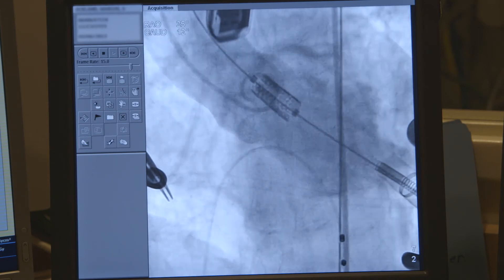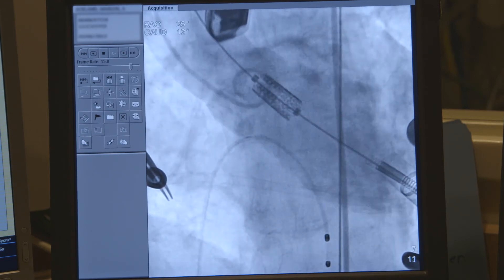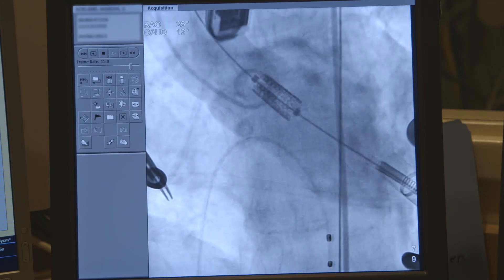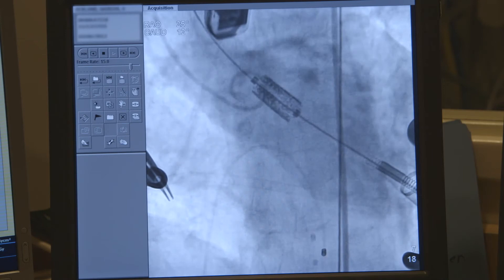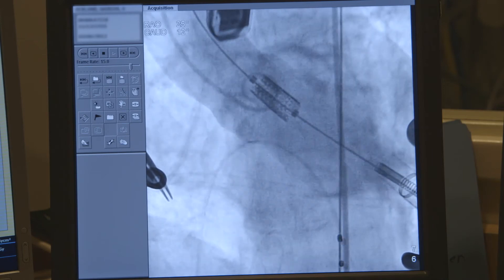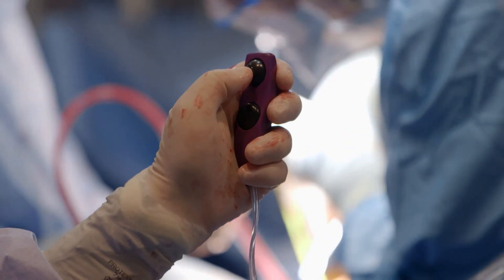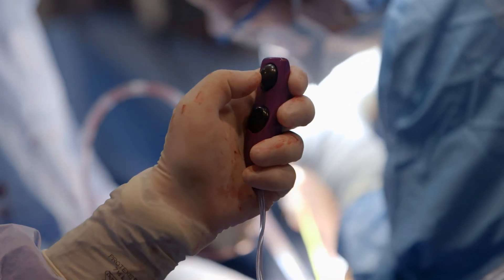Localization of the prosthetic valve to the native valve is very important and that's usually done with injections of contrast. Sometimes you need a little bit of contrast and a small puff, other times you need larger injections. With the ACIST system, the advantage is that in your hand you can control both the rate and volume of injection very precisely, so that you can minimize the amount of contrast given but yet get good visualization of valve position.